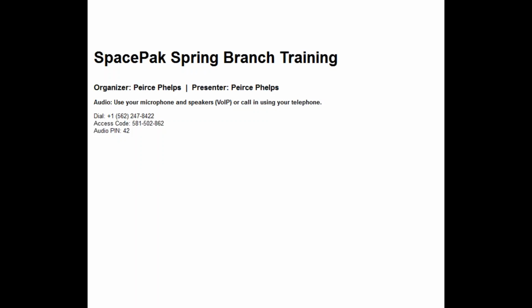First thing is a quick review for those folks who have been involved with SpacePak in the past but may have forgotten a few things. SpacePak is small duct high velocity air conditioning. So how does it work? We distribute air through a small 2-inch opening at a very high rate of speed. And while it's moving rapidly, it's actually at about half the CFM of a standard ducted system.